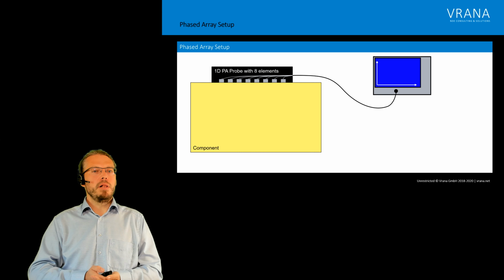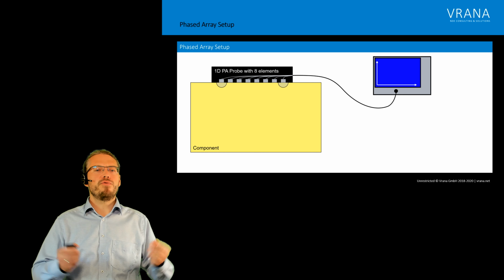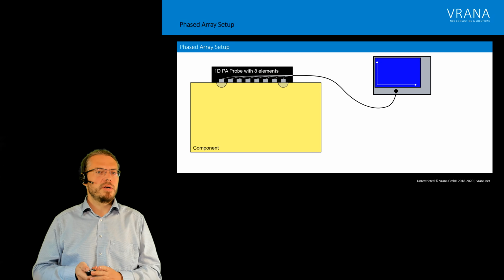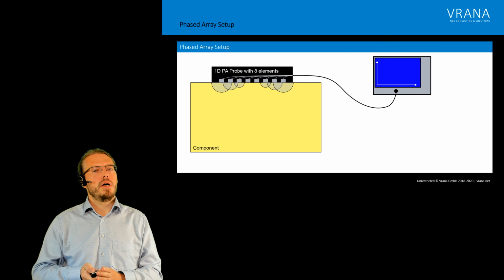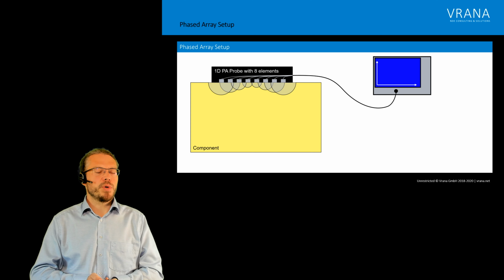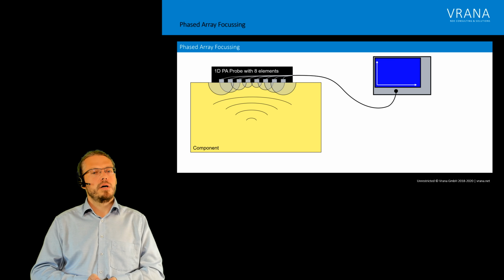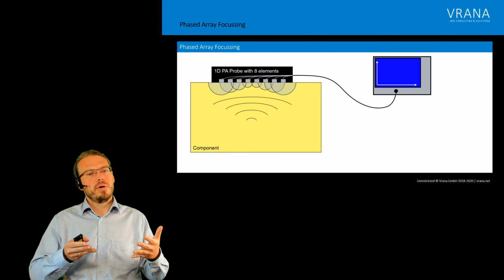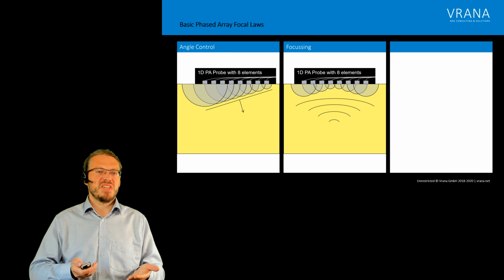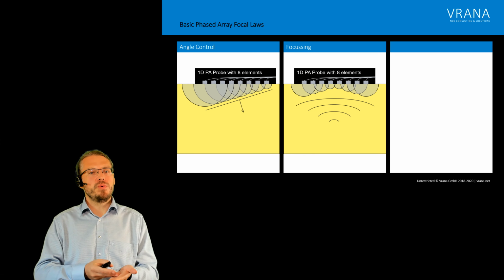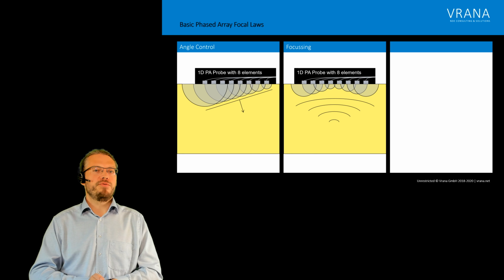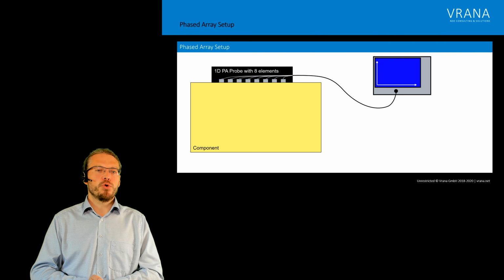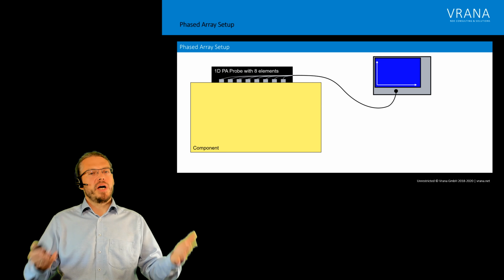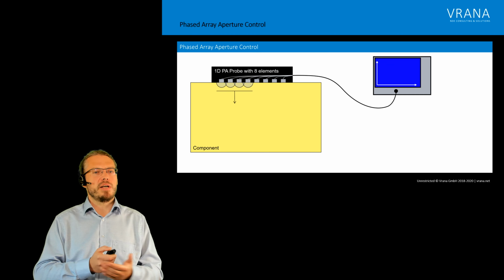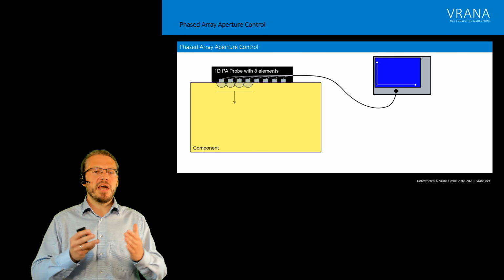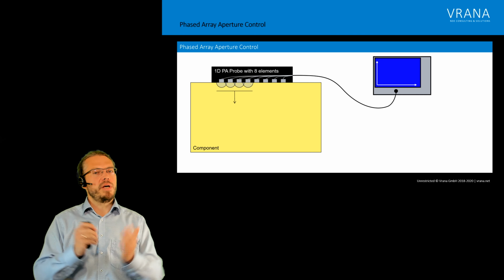Now, the second example I want to show you: in this case, we first fire the outermost 2 elements. Then we go inwards until we reach the middle. What you can see happening is that we are focusing. We are producing a focused wave. So this is our application number 2, our use case number 2 for our phased array. And for sure, we do not have to use all 8 elements. We can also use a subset of those 8 elements and create a smaller aperture with a bigger opening angle.